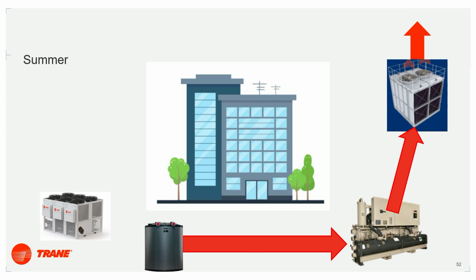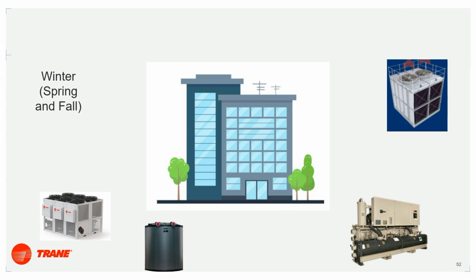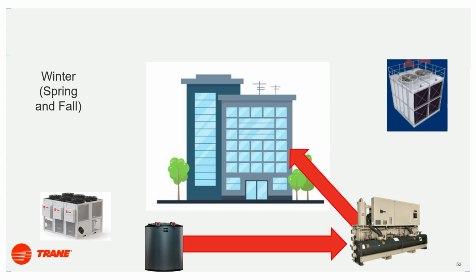At night, you need to recharge that battery by making ice again so we can use it the next day. It's utility rate arbitrage. We are shifting demand off our peak to lower our peak demand usage and our demand charges and lower our utility costs. So what if we tried to reverse this cycle? If we were trying to use this for heating, our thermal battery would be charged when it was full of water. So in that morning warm-up, we are going to extract heat out of the water to heat our building. When you extract heat out of your water, what are you doing? You're making ice, right? We like to play with the phase change property of ice because it's a very dense form of energy. So we don't need massive tanks.